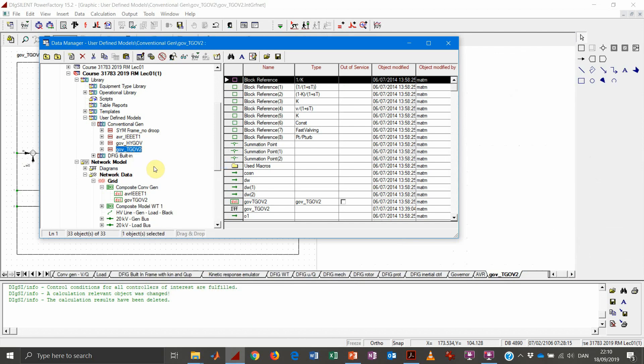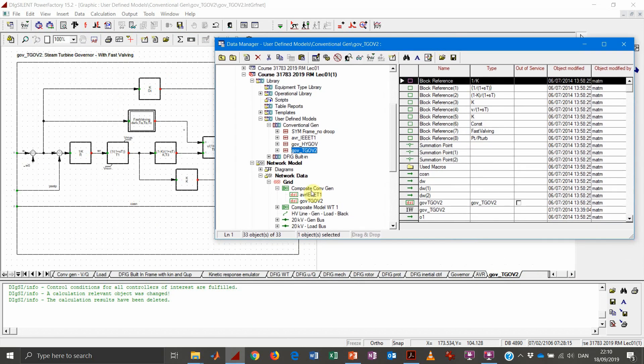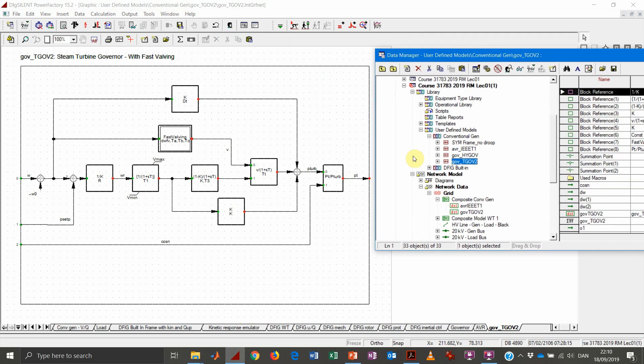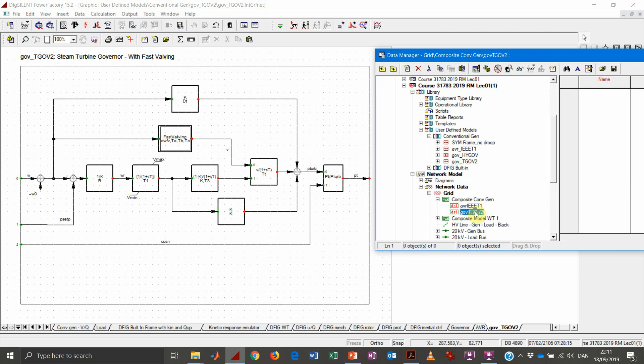To get an insight into the block diagram for the governor and AVR, we can show the graphic to see what is included in our governor. We have a block diagram with some gains, some first-order filters, other types of transfer functions, and possibly different types of nonlinearities, if they are necessary to model the dynamics. For each block we have a certain number of inputs and outputs. These blocks have constants whose values are defined inside the governor common model.